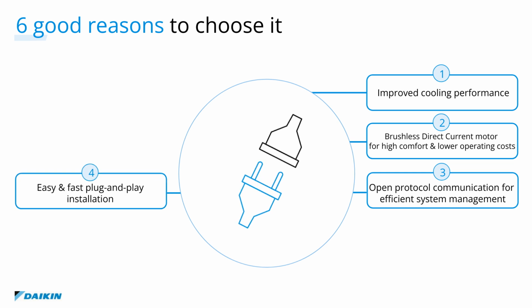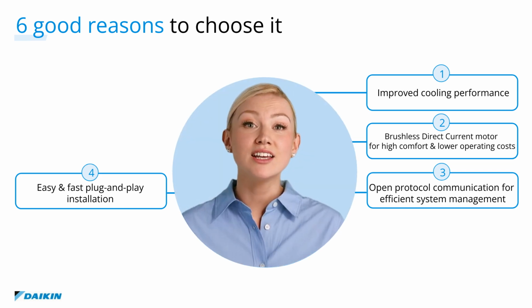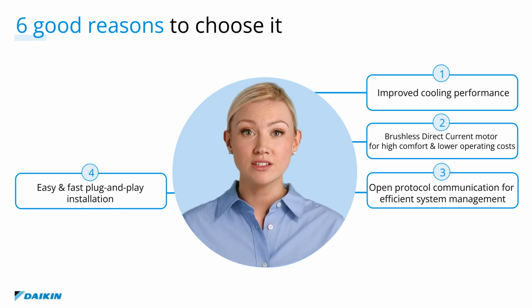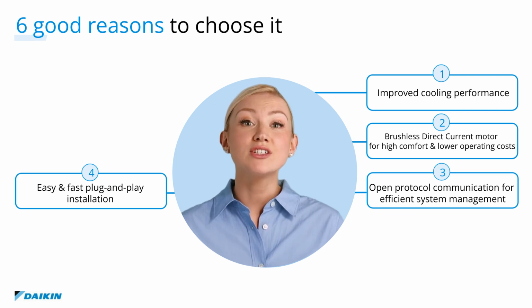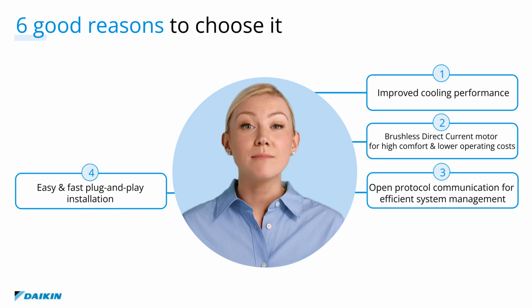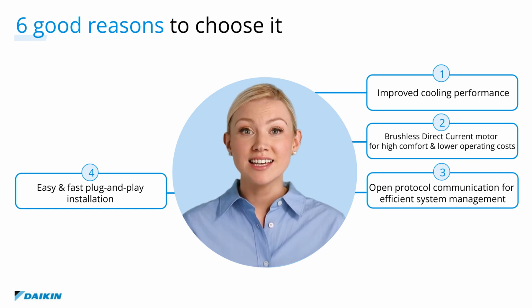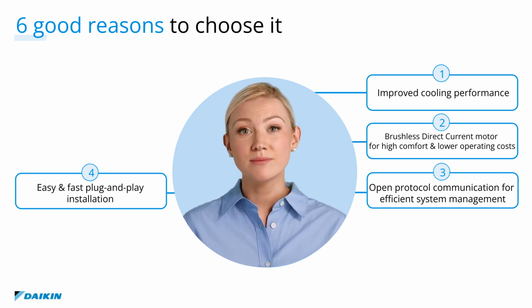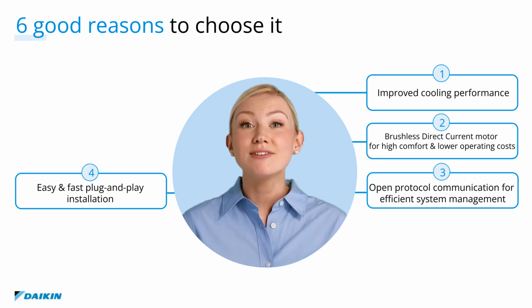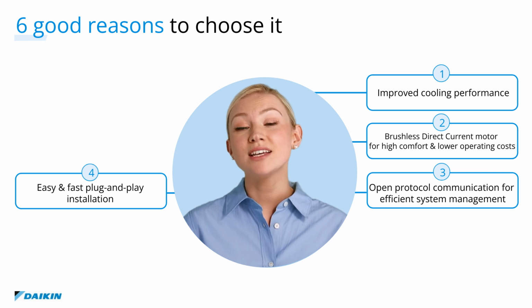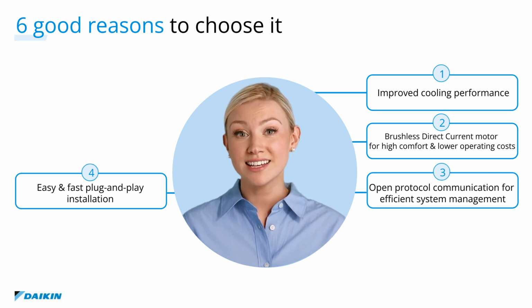Equally important is installation time. This unit comes with factory-mounted valves and an integrated drain pump, significantly reducing on-site work. This pre-assembled approach saves time, reduces costs, and limits the risk of errors during installation. In large projects where dozens or even hundreds of fan coils must be installed under tight deadlines, this can make a real difference. Faster commissioning and fewer variables help ensure a more predictable, reliable installation process.